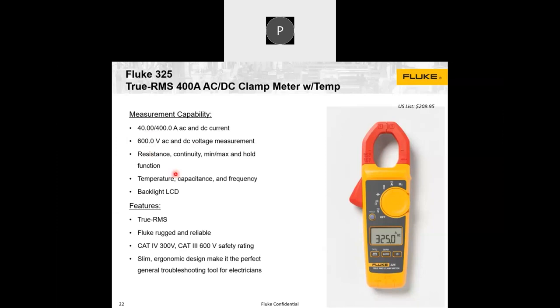That's why it's very easy to use. You can also see the category rating here. It can go up to category 4 locations with up to 300 volt measurement, and category 3 locations up to 600 volt measurements.